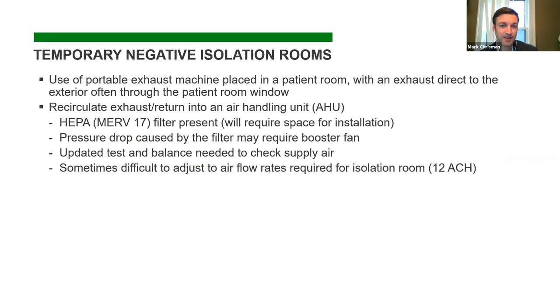Some of the issues: you're going to need space to install that filter in the ductwork, and a lot of older facilities just don't have the space above the ceiling to do that. Another challenge is once you put the filter in, you've got an additional pressure drop in the return duct, so you may have to install a booster fan to help boost the pressure.